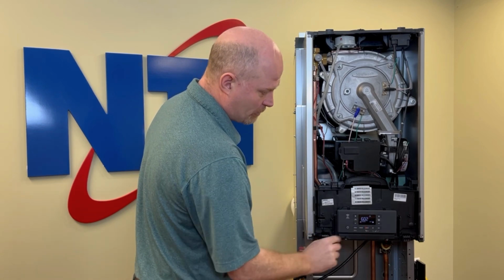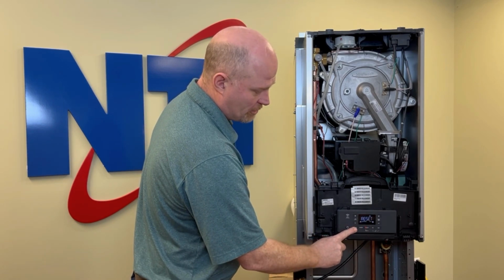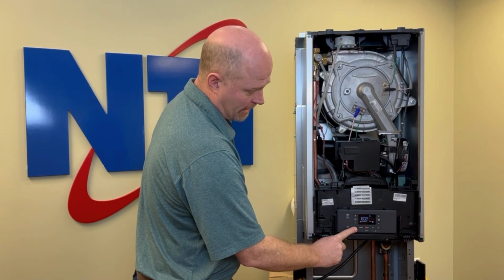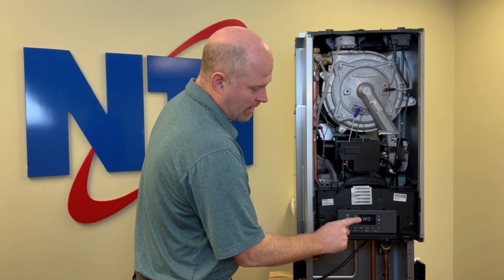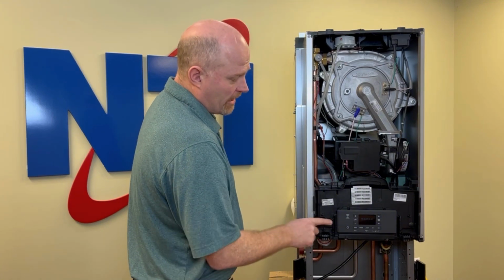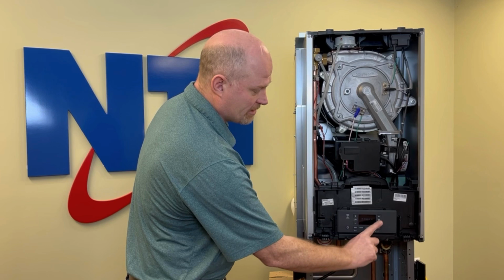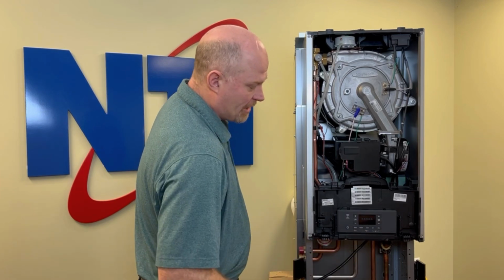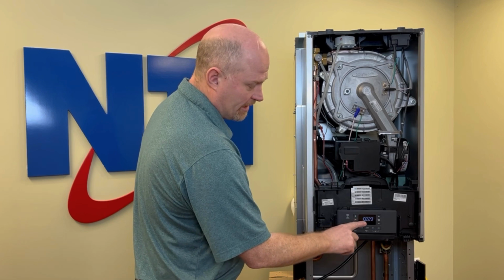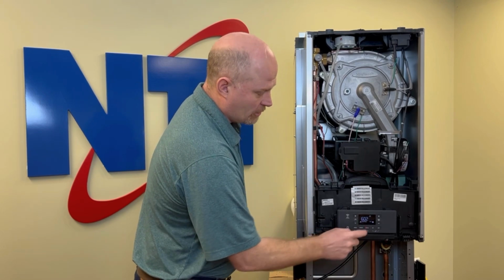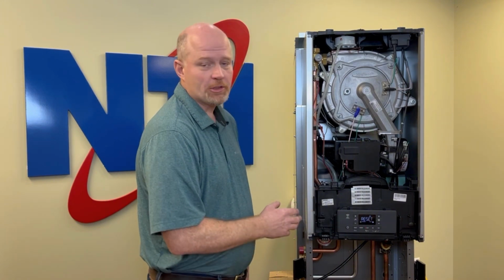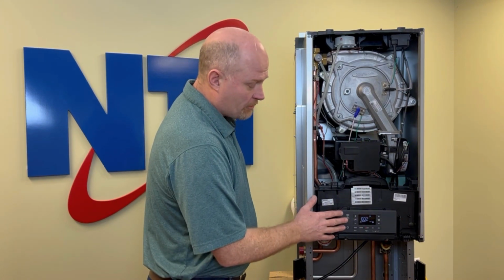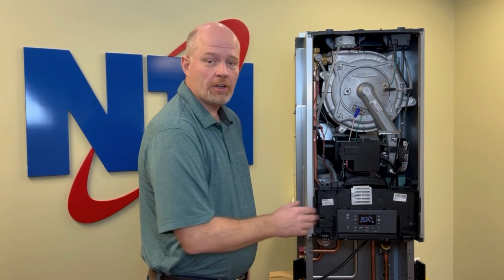The first thing you'll want to do when you get this error code is go in and check the temperature of the boiler. To do that, press and hold the menu button for 5 seconds. The menu will change to say info, and at that time, you can navigate up using the plus button to menu number 10, and you can see the current flue gas temperature. In this case, it's a reading of 229 Fahrenheit. What that means is, no matter how many times we press the reset button, the boiler will not reset the code because the flue gas temperature is out of range. You cannot reset this code until the temperature drops below 149 Fahrenheit.